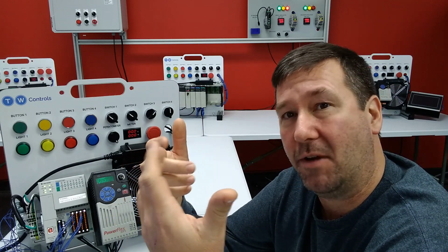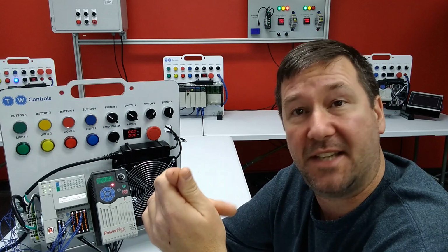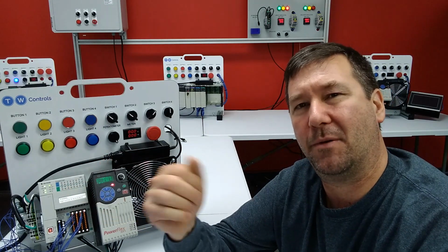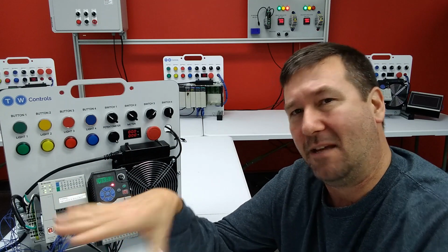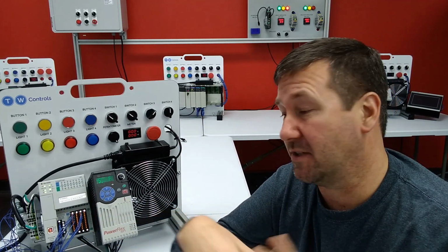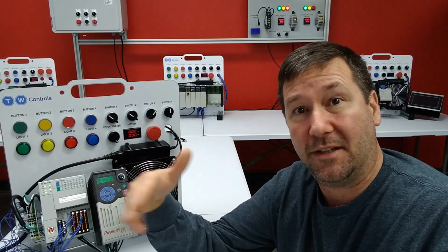Besides the PID series, we've only really worked in the continuous task. The PID was done in a periodic task because we wanted it done every so often. And actually, that may be what I would do: create a periodic task of a low priority and put all the GSVs in it. I'm not sure how I would really do it; I'd have to think about it. It would depend on the particular application. But I definitely wouldn't have the GSVs continually doing it.